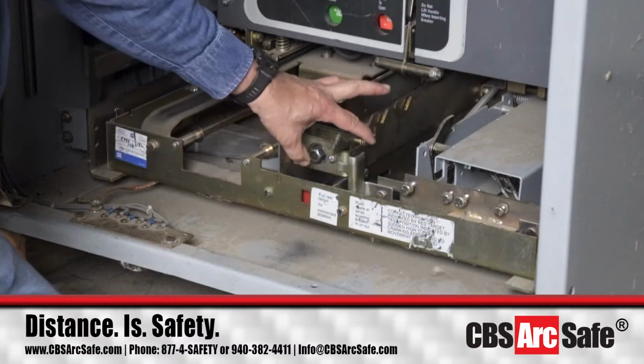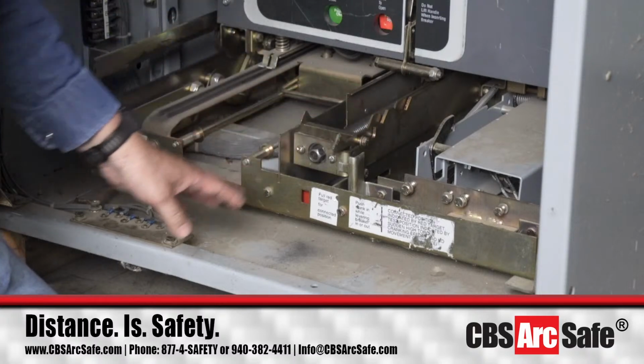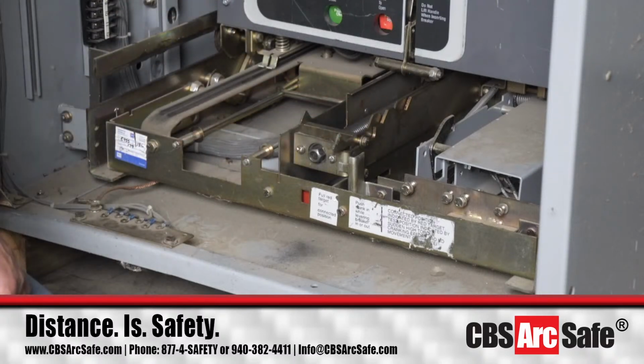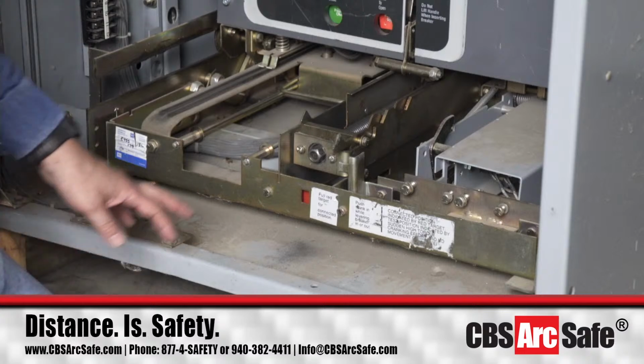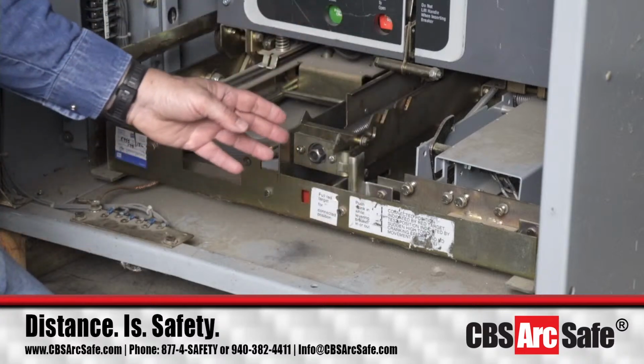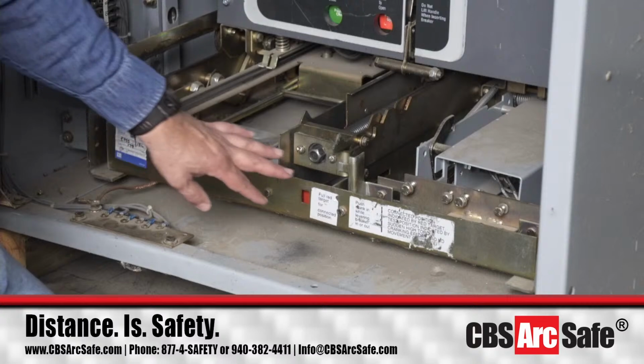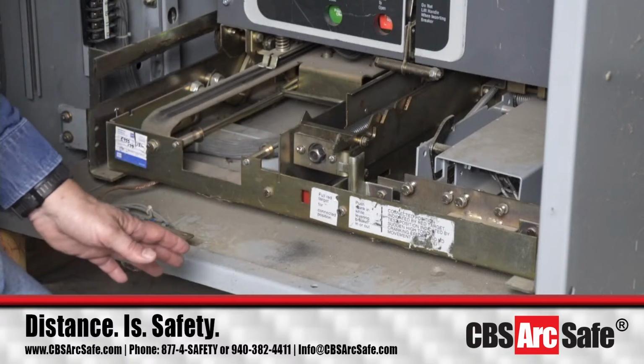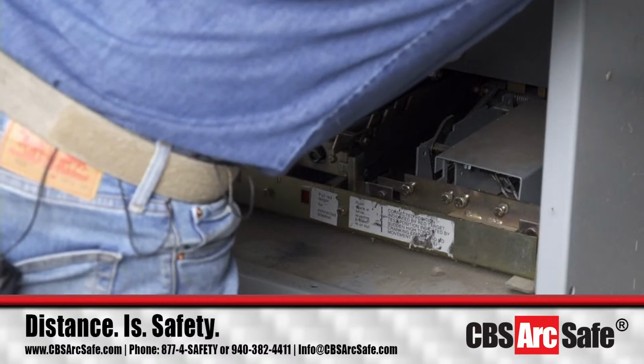Okay, now this basic part of the racking mechanism is used on 5 kV, 15 kV, and 38 kV breakers. It'll look different around the frame and everything based on the size of the breaker, but this general area right here remains the same. So let me get our racking tool over here, and I'll work to get it installed.